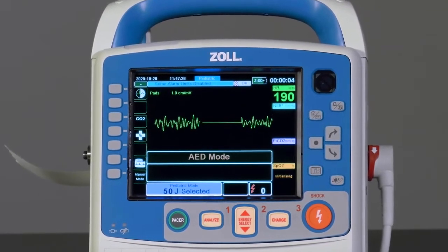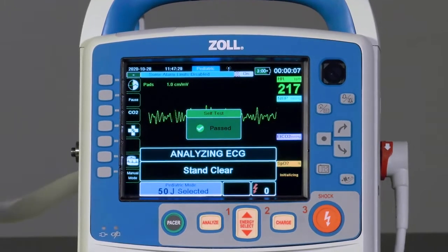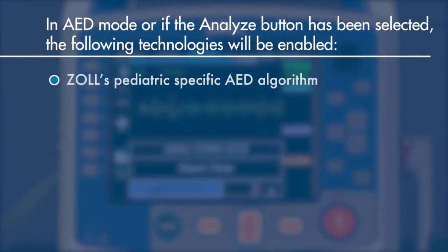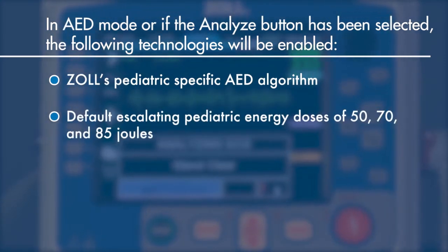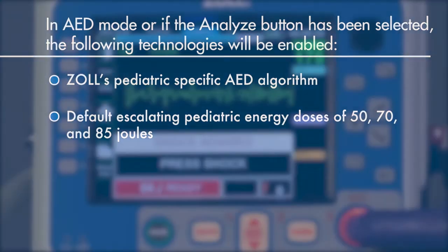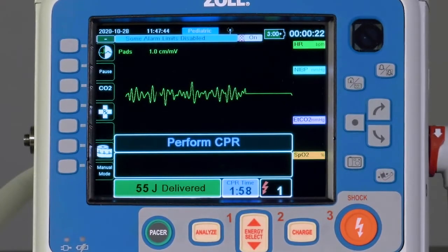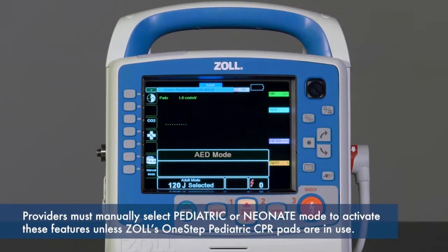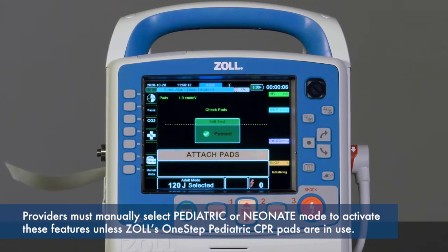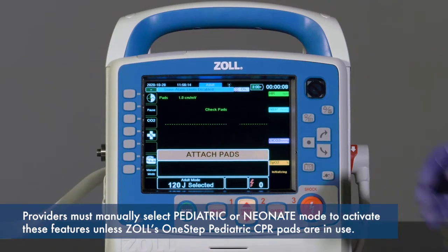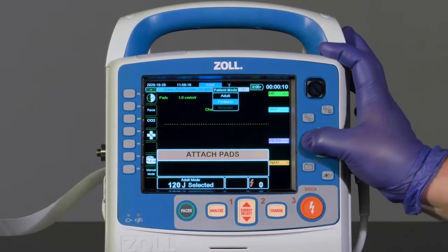If the X-Series Advanced is being used in AED mode, or if the analyze button has been selected, it will automatically enable ZOLL's pediatric-specific AED algorithm and default escalating pediatric energy doses of 50, 70, and 85 joules. It is important to note that providers must manually select pediatric or neonate mode to activate these features, unless pediatric one-step CPR electrodes are in use.